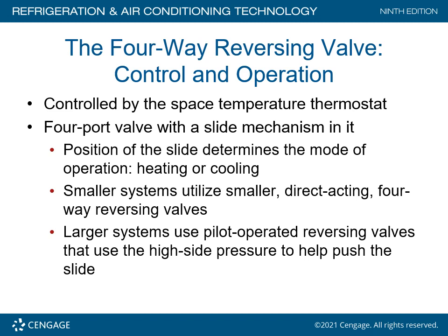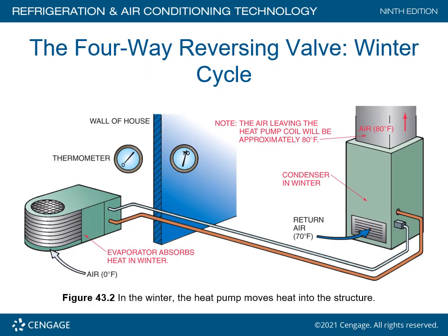Four-way reversing valve control and operation. Controlled by the space temperature thermostat, it is a four-ported valve with a slide mechanism located internally. The position of the slide determines the mode of operation, either heating or cooling. Smaller systems utilize smaller direct-acting four-way reversing valves. Larger systems use a pilot-operated reversing valve that uses the high pressure in order to push the slide. In this picture here, we're showing the four-way reversing valve in the winter cycle.